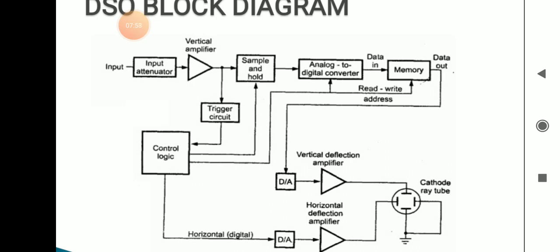In this mode, input signal is not triggered at all. So a fast changing signal is displayed on the screen as if it is changing slowly, because you are not going to use a trigger here. That's why you cannot display a higher frequency signal. The signal will move from screen right to left, so we can call this a very slow moving signal.